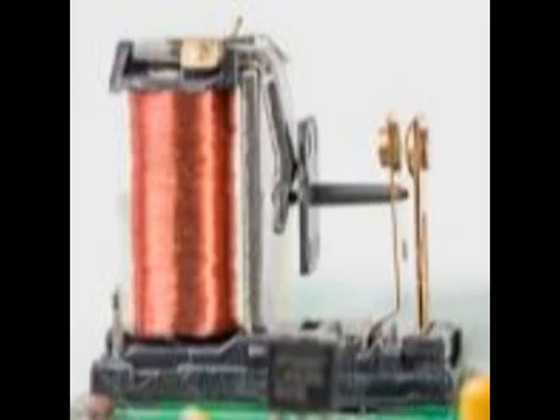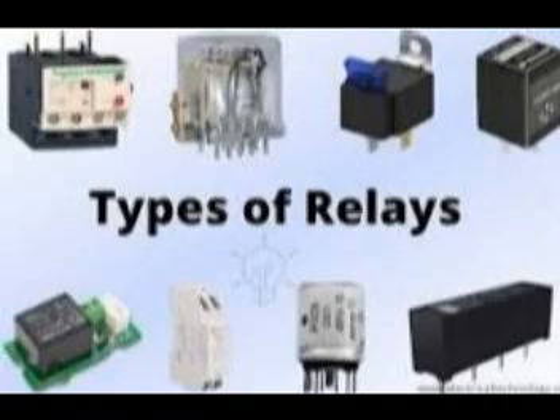Relays still have a critical role in safety-critical logic, especially in places with nuclear radiation, where semiconductors can be unreliable. Why is that? That's a key point. Semiconductors, transistors, and integrated circuits are quite vulnerable to the effects of high levels of ionizing radiation. It can cause errors, malfunctions, even permanent damage. Relays, being electromechanical, are inherently much more resistant to those radiation effects. Their operation depends on magnetism and physical movement, not delicate silicon junctions. So they just keep working. Pretty much. This makes them absolutely vital in applications where failure is just not an option and radiation is present.